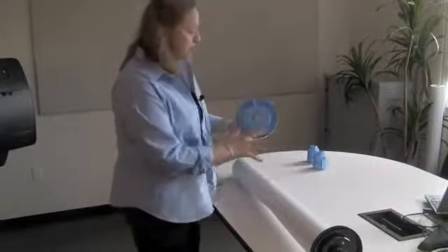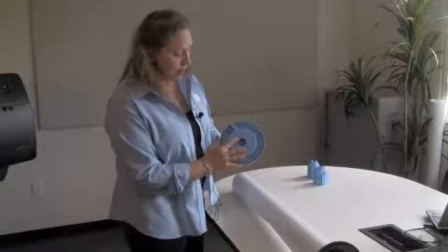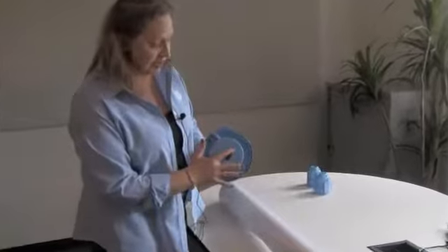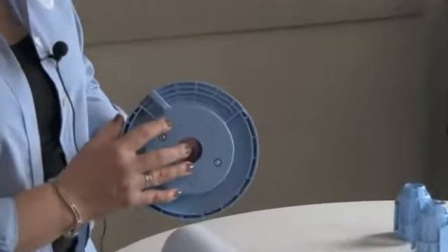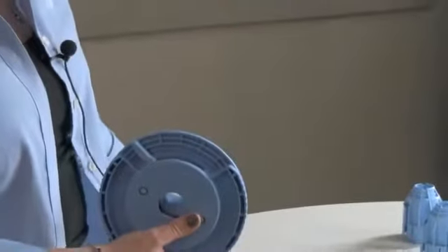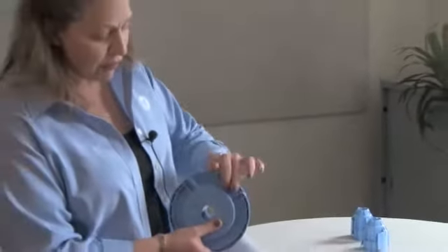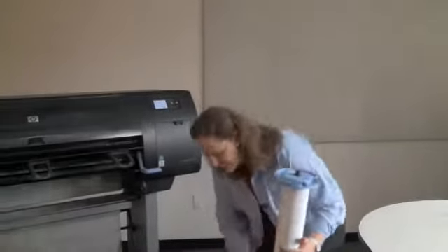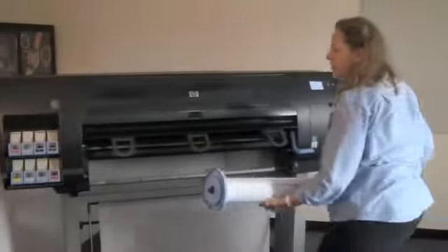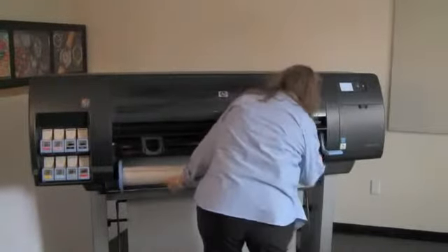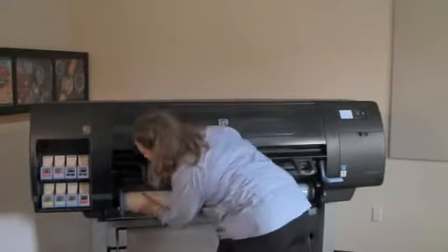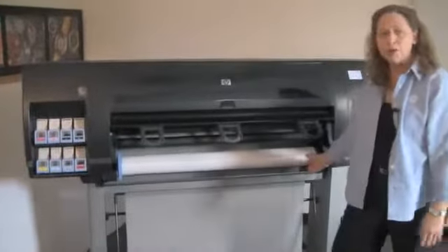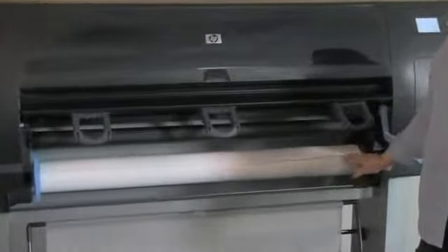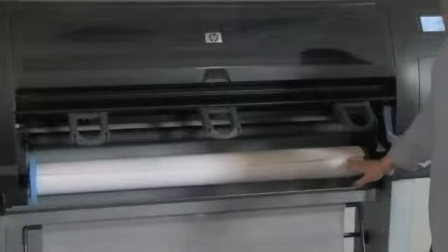And then on this blue movable end of the spindle, I want to point out the fact that there is an open and a locked position. Make sure that you load it in the open position, and when it's nice and tight up against the media, move this lever over into the locked position. So once the cap is nice and tight and it's in the locked position, we're ready to pick up this loaded spindle and take it to the machine, where we insert it into the device. I hope you were able to hear both of those clicks. That means that the media is in position and it's ready to load into the machine.